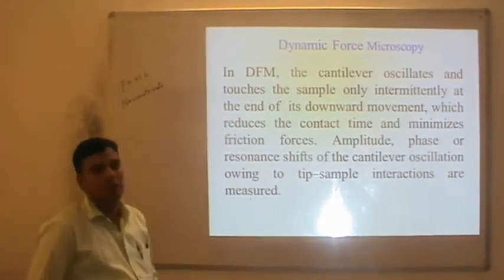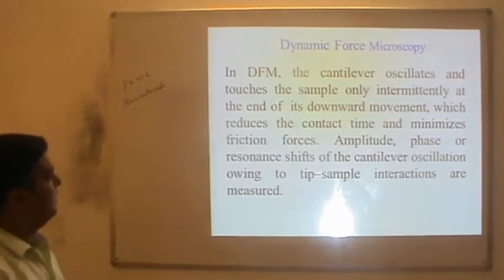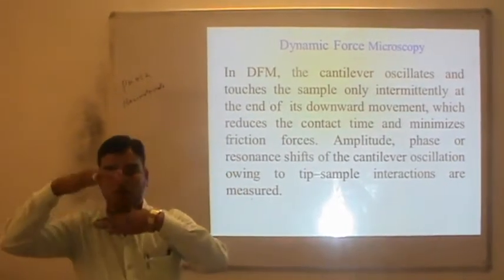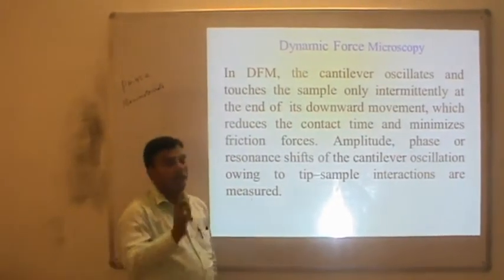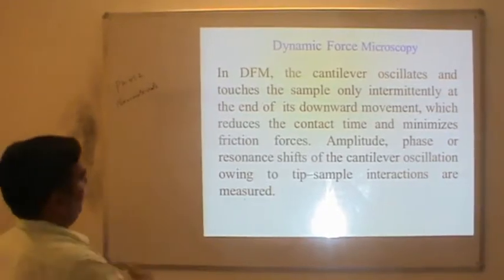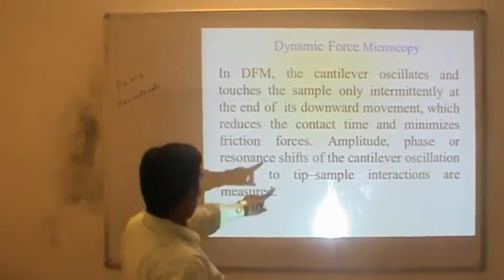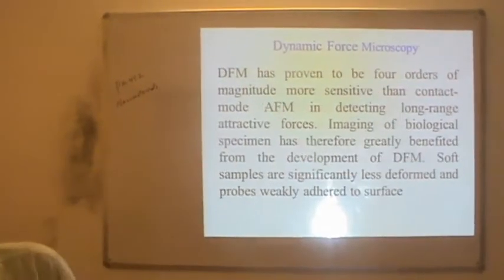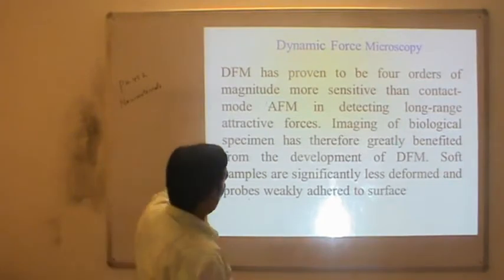Another technique based on the AFM principle is Dynamic Force Microscopy (DFM). In DFM, the cantilever oscillates and touches the sample only momentarily at the end of its downward movement — it is in tapping mode. This reduces contact time and minimizes friction. The amplitude, phase, or resonance shifts of the cantilever oscillations from tip-sample interactions are measured. DFM is four orders of magnitude more sensitive than contact mode AFM in detecting long-range attractive forces.